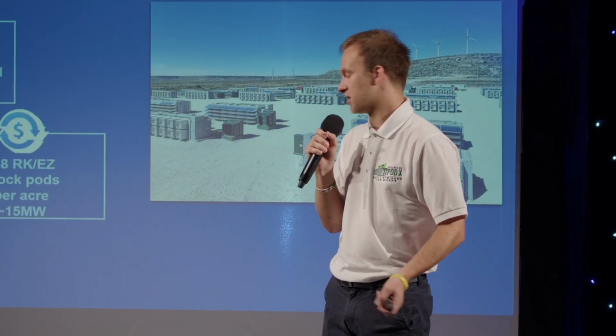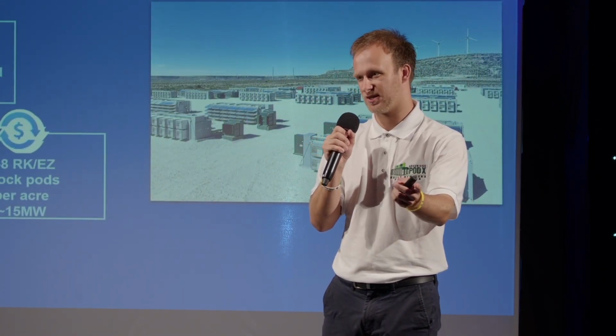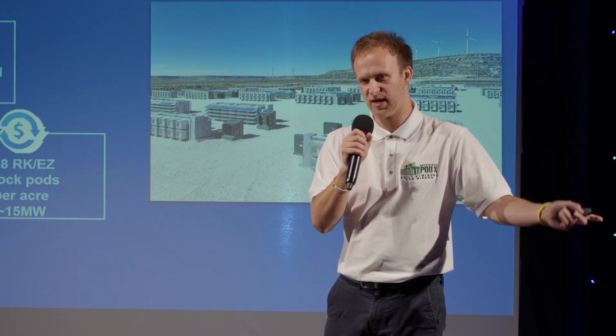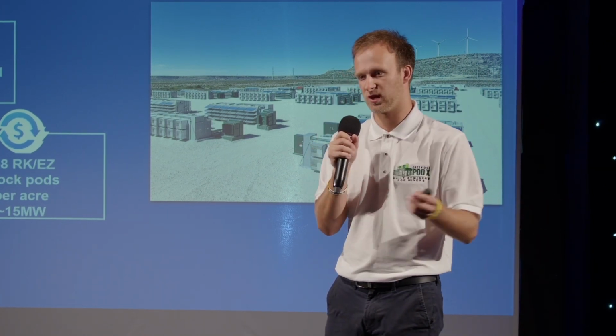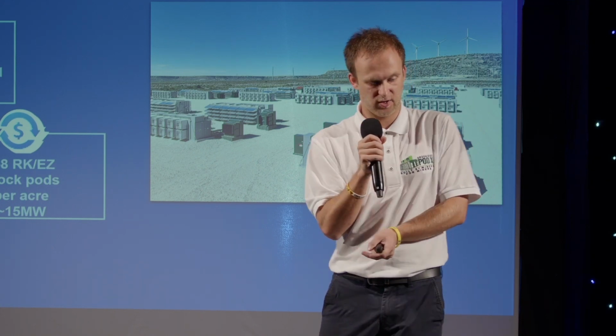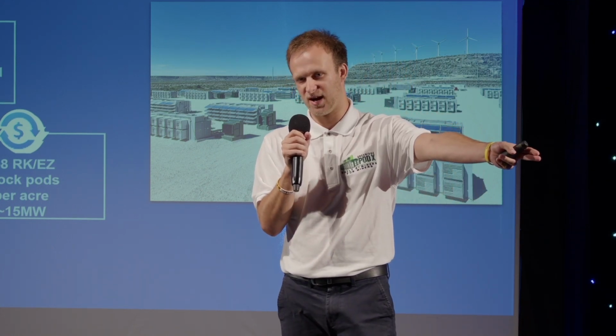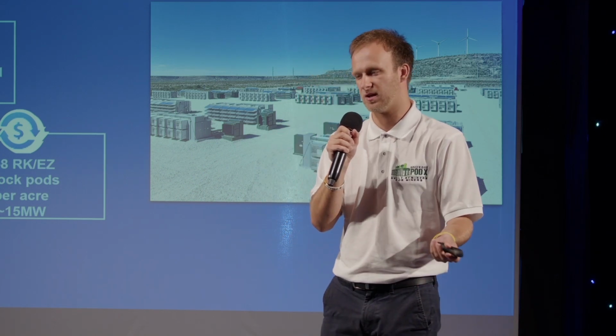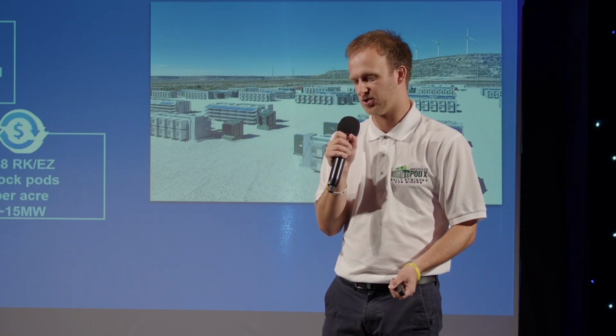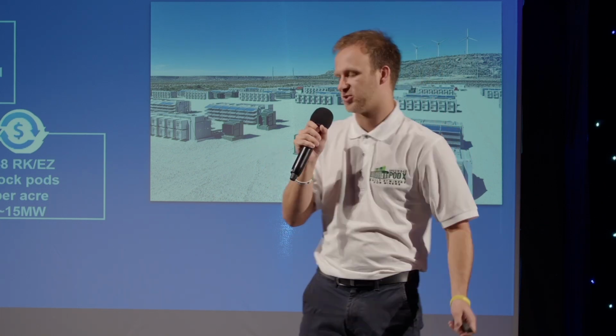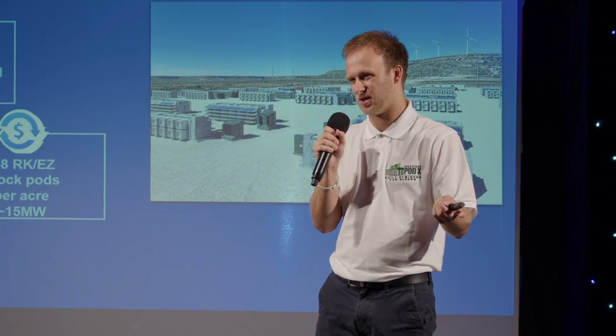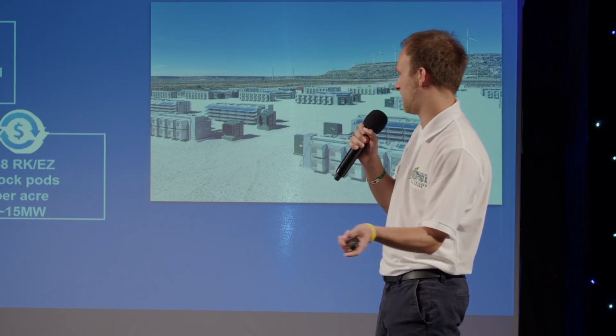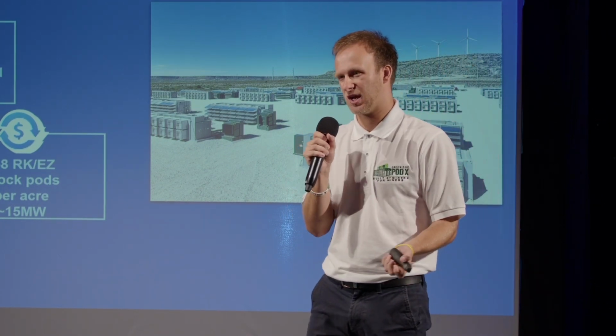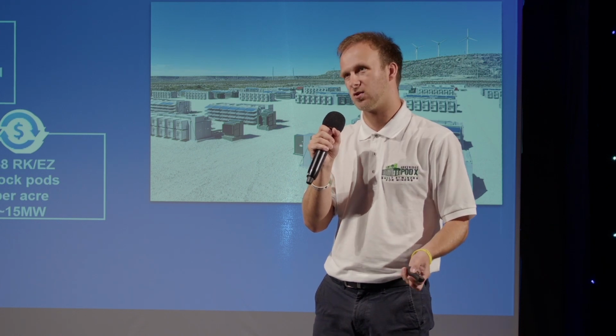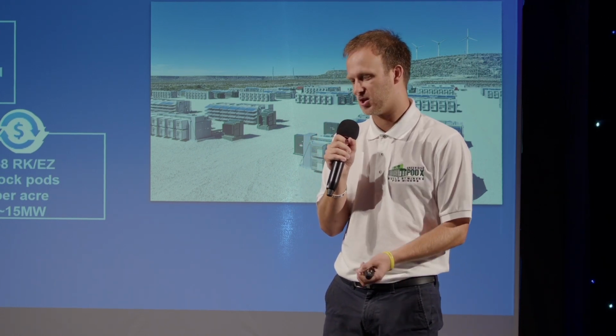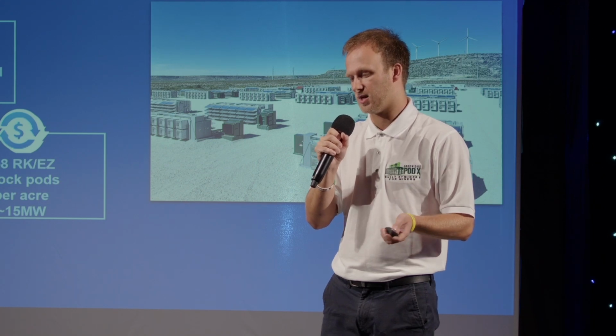Limited pod density. Because of the direction that you're exhausting out of a streamlined pod, you aren't able to space it as close as you might if you were doing a different type of airflow. If you're pointing your exhaust at an adjacent pod and it's way too close, you're going to get that hot air recirc and it's going to overheat that pod at lower temperatures. So you're really limited. What we've measured is about 75 to 100 feet in between exhaust on these streamlined pods, which equates to about 15 megs or 6 to 8 RK or EZ block pods in an acre area. So in our opinion, it's pretty low, and you could do a lot better with different airflow movement.